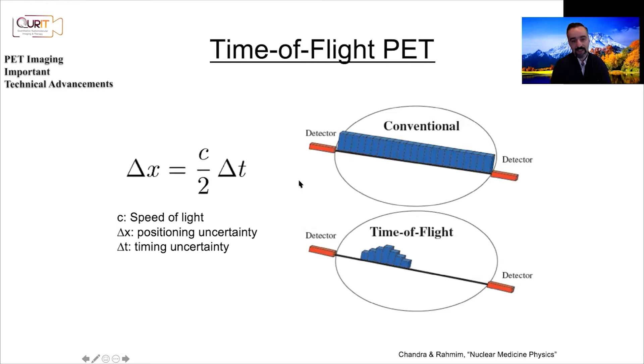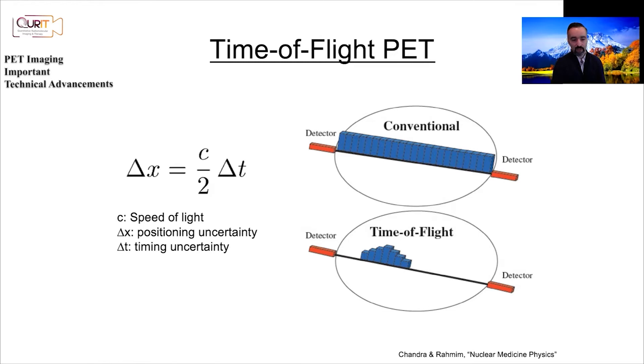As of 2021, the timing resolutions we achieve are on the order of hundreds of picoseconds, and that only allows us to narrow the position down to centimeters, not one or two millimeters. The positional uncertainty is given by Δx = c·Δt / 2, where c is the speed of light and Δt is the timing uncertainty. There is a factor of two because we are dealing with two detectors — students are encouraged to prove this themselves.